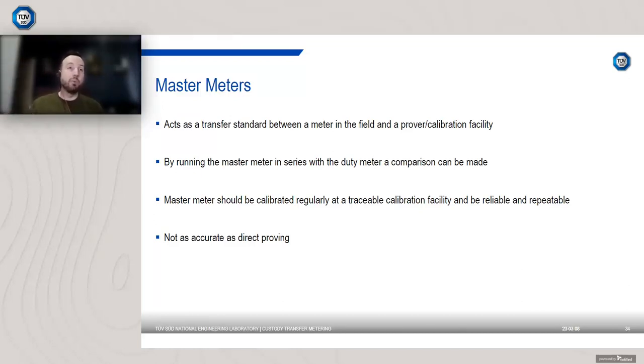A good example of master meter use is positive displacement meters. So they've been used for years to verify petrol pumps. We talked about PD meters being very reliable, repeatable. They're not sensitive to installation effects, so that makes them ideal to be used as master meters.